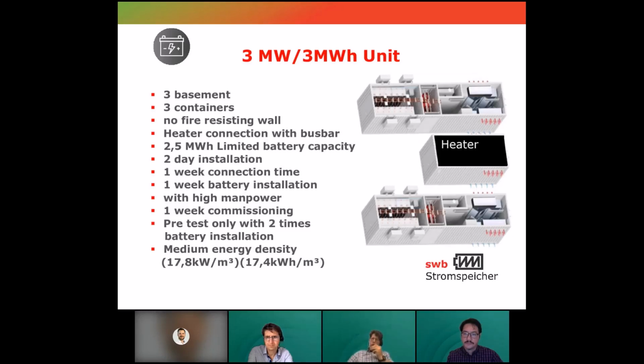So with this, we created a 3 megawatt unit for FCR. You can see here on the right side the inverter system, in the middle the mid voltage connection with the transformer and the switchgear, and on this side the battery systems with the HVAC systems in, and the fire detection system also in, the heater in the middle, and a second container to get then the 3 megawatt systems together.